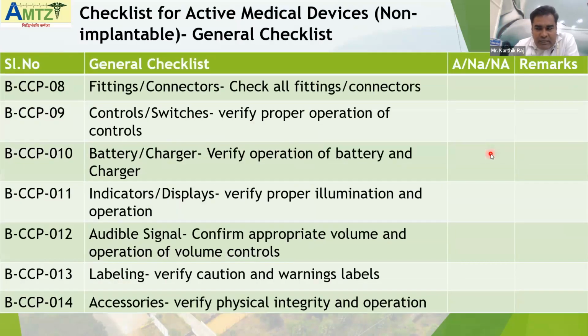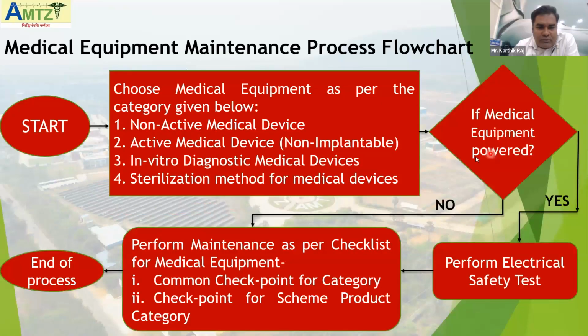Coming back to that same flow chart, where I was saying, perform the maintenance as per the checklist for the medical equipment. In the scheme, we have defined a common checklist for each category. For non-active medical devices, a common checklist is there. For active medical devices, non-implantable, another common checklist is there. Then for IVD instruments, another common checklist. And for sterilization methods for medical devices, a common checklist is there. Plus, each scheme product category has its own checklist, except the non-active medical device category, where there is only one common checklist.